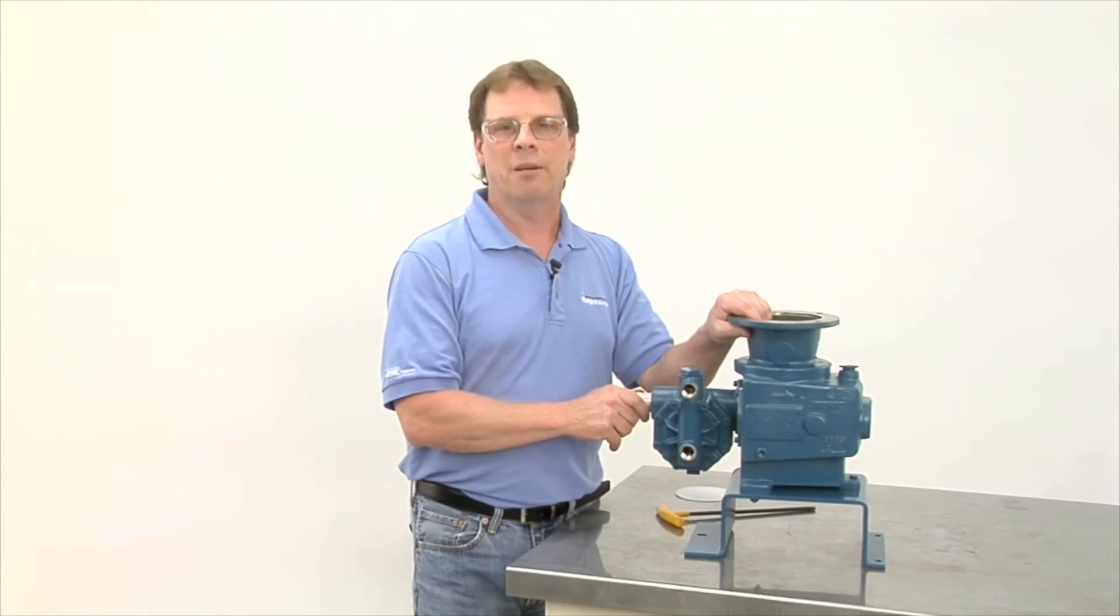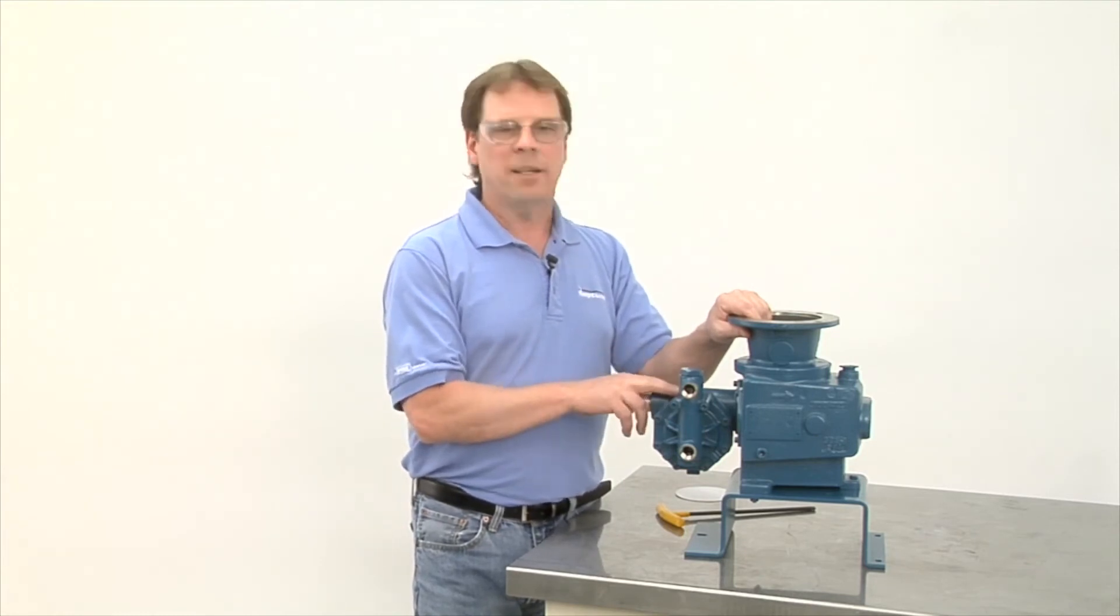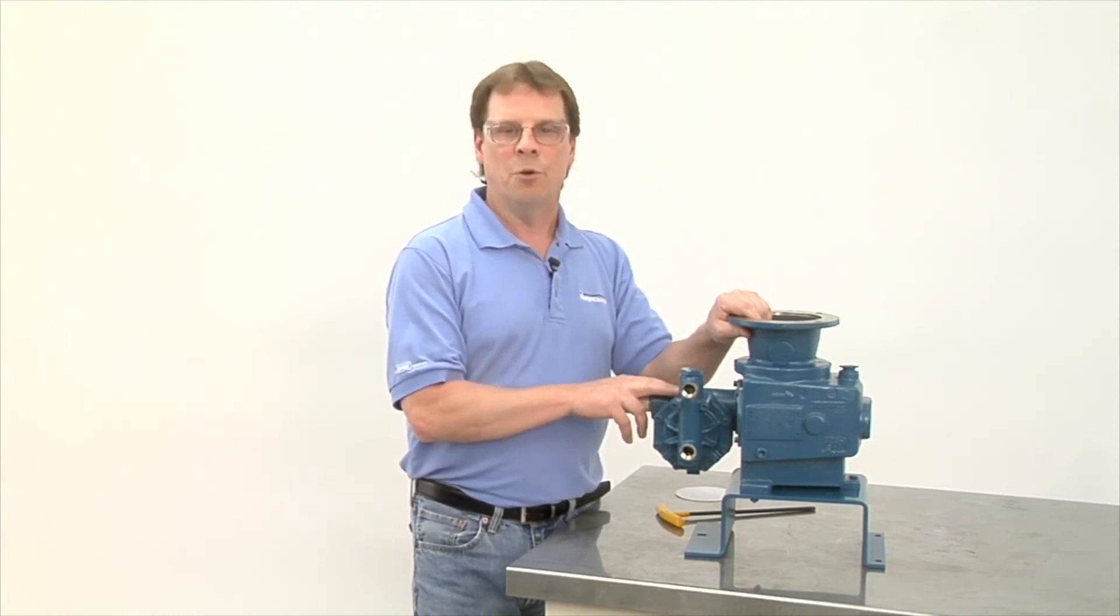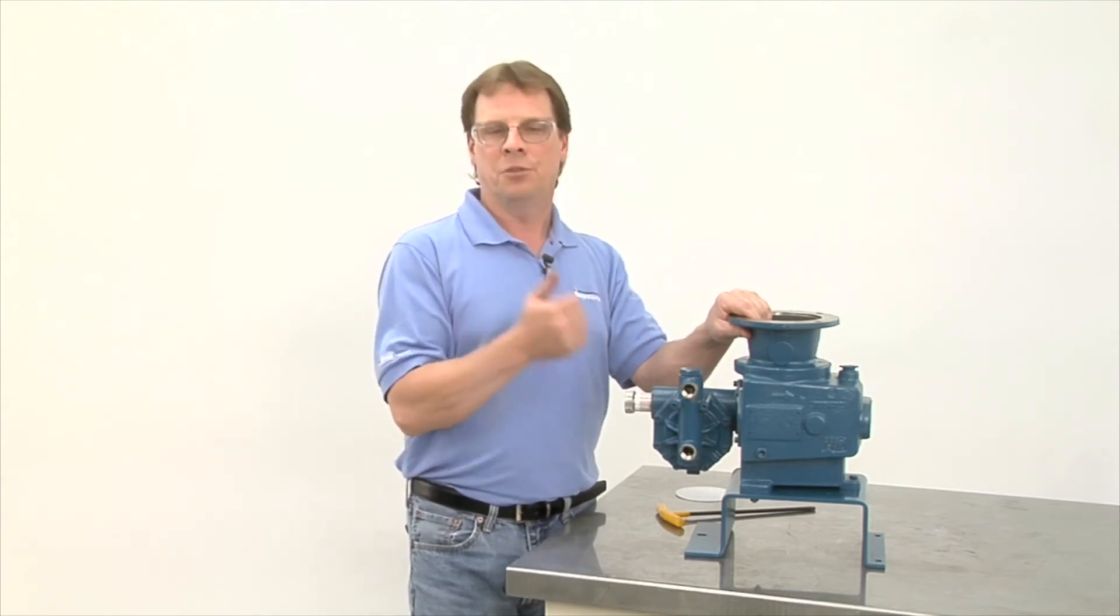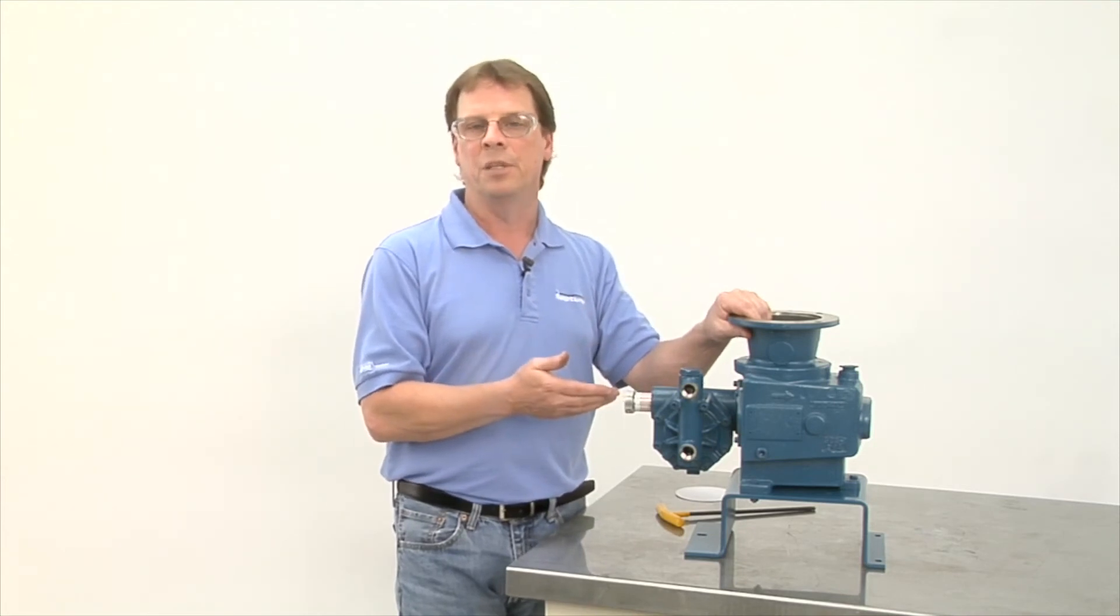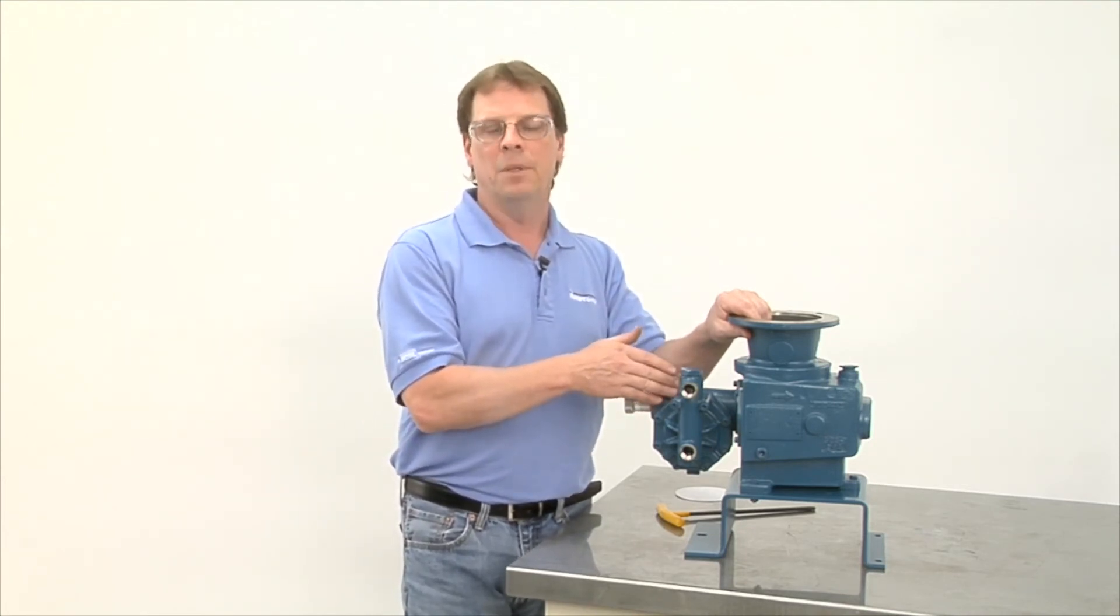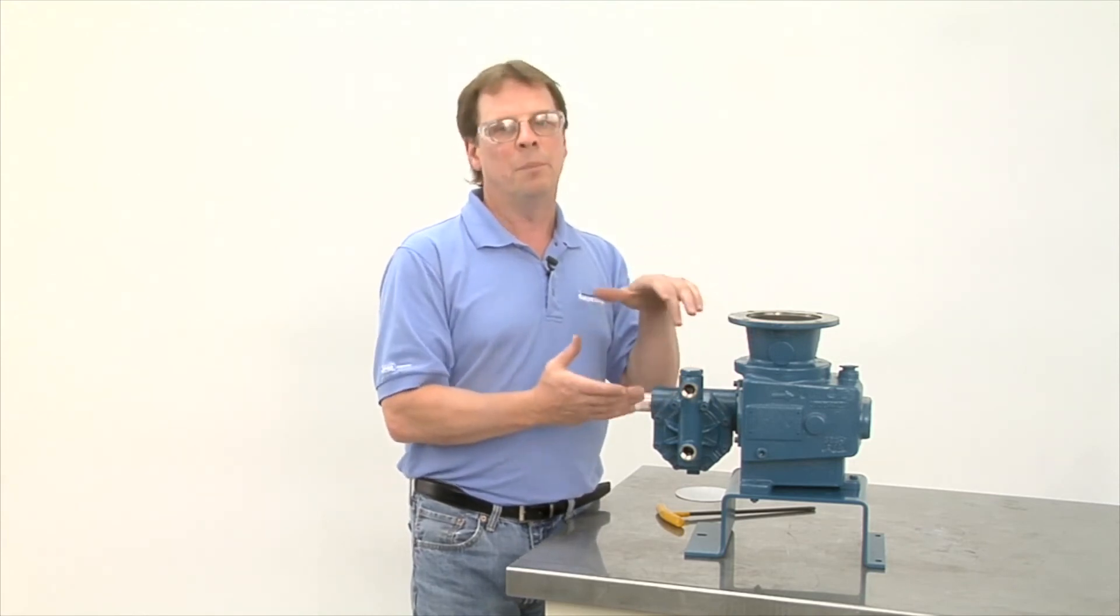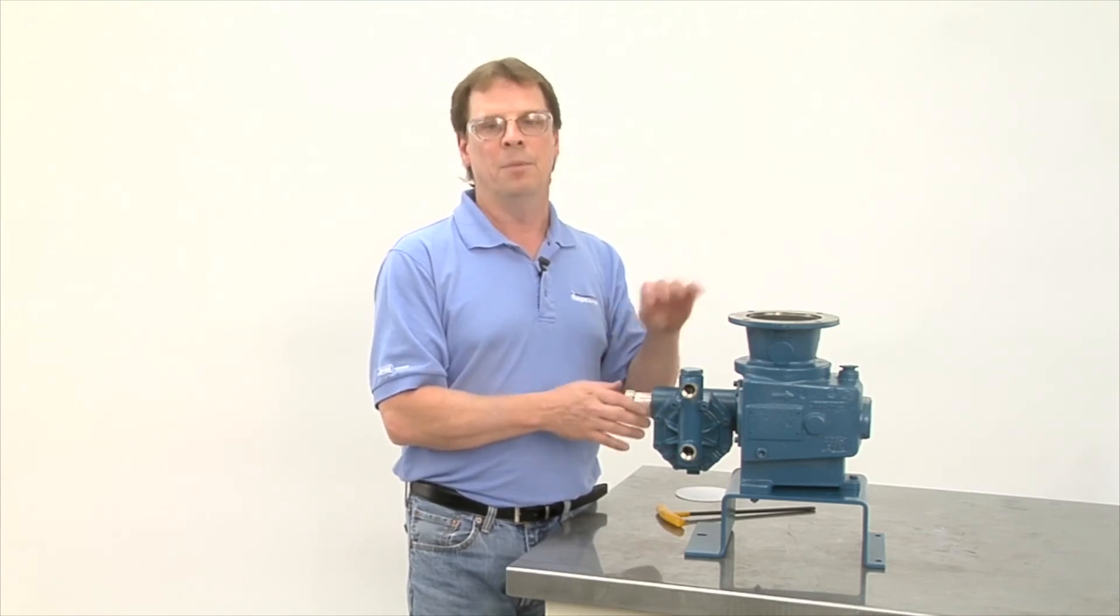And that's how you change a diaphragm in a 500 series pump. Footnote, that diaphragm change also goes into our other pumps, our other hydraulic pumps. The 600 series, the 6000 series, and the 560 series. It's all basically the same type of diaphragm, except for things are just a little bit bigger on higher flows, but it's the same premise when changing the diaphragm.